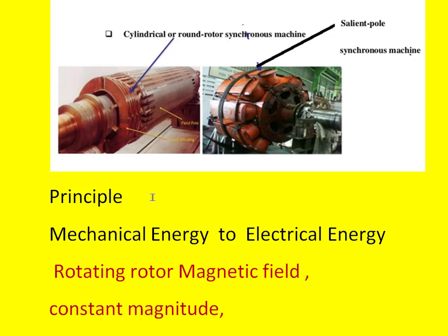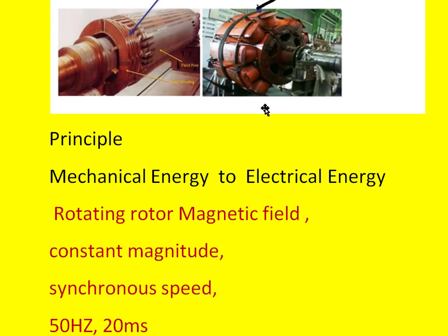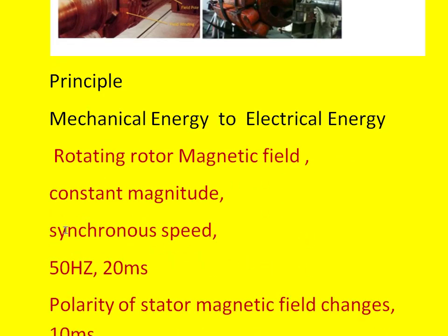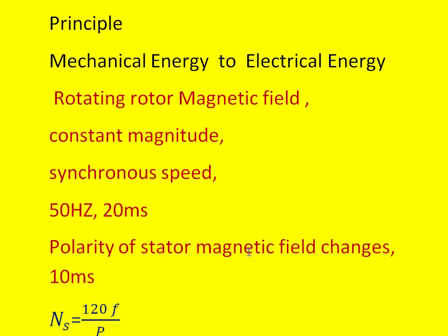Coming to the principle of the synchronous generator — in general, the definition of a generator is that it is a machine that converts mechanical energy into electrical energy. Some key terms here are: rotating rotor, magnetic field with constant magnitude, running at synchronous speed. The synchronous speed can be obtained using the formula 120f divided by P, where f is the frequency and P is the number of poles on the rotor.